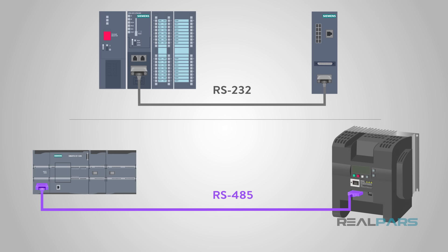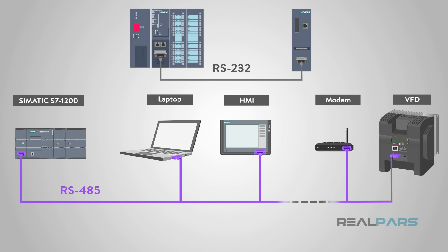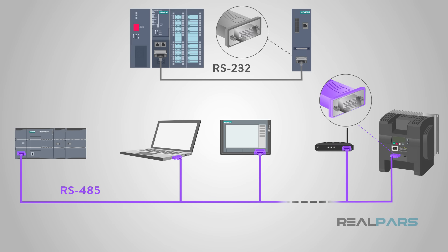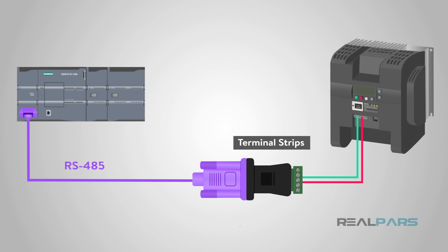Let's recap what we now know about RS-485. It is faster and much more versatile than the older RS-232. Users can utilize a longer cable — up to 1200 meters or about 4000 feet. The greatest feature of RS-485 is the ability to connect up to 32 devices on one system, whereas RS-232 could only handle one at a time. There is no standard connector for the protocol; most manufacturers utilize a DB9 connector, or you can simply use a terminal strip. All in all, RS-485 really made full automation possible with its ability to connect so many devices at once.